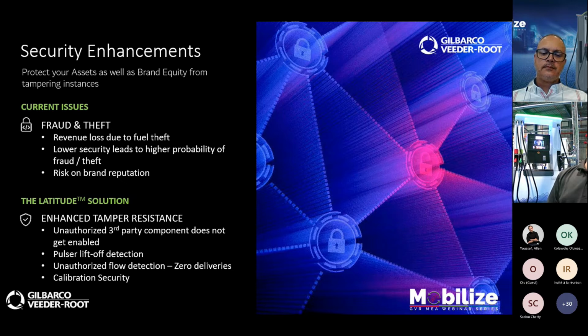There's also security around the calibration we've implemented. It's a matter of cutting a seal, then having to access a certain switch to allow calibration to be changed, and there's still a password on top of that. So there are quite a few layers to get through when it comes to protecting our calibration.